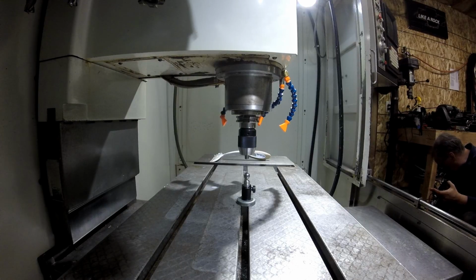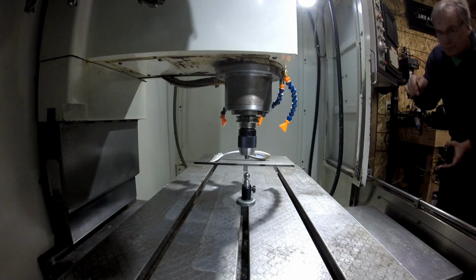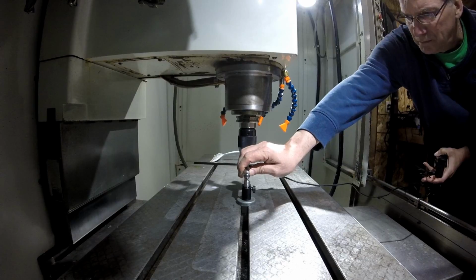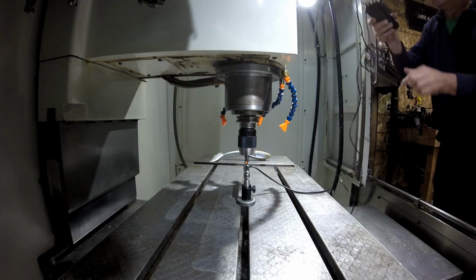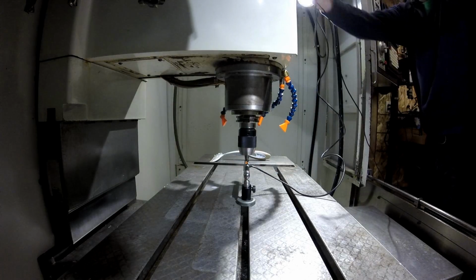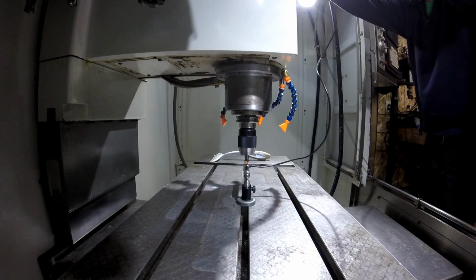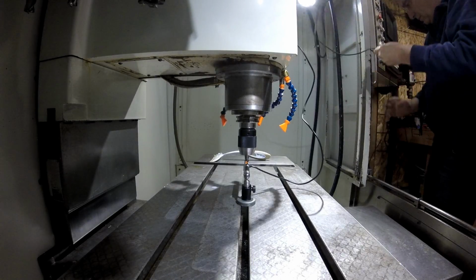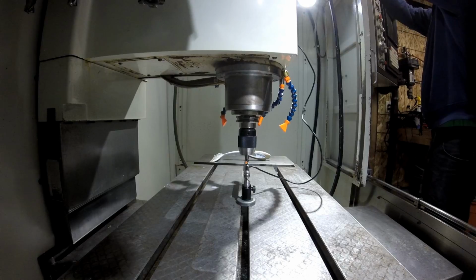So we're installing the ball bar in the machine. There's a base that just magnetics down onto the table and has a metal ball. Then there's a receiver that goes in the spindle that has a cup. The ball bar has a cup on one side to go on the ball, and a ball on the other side. Inside the cups are magnets, and there are little copper bronze fingers, so that there's kind of like a bearing surface, so it's very accurate and it doesn't move around.